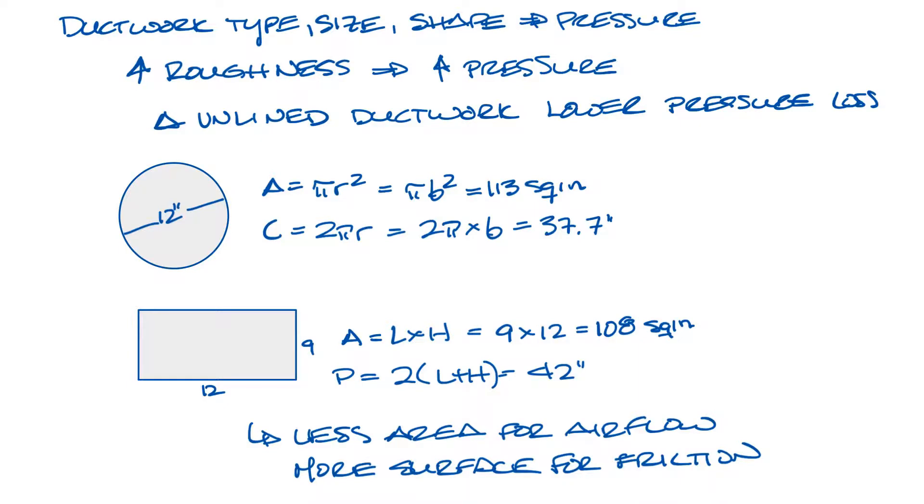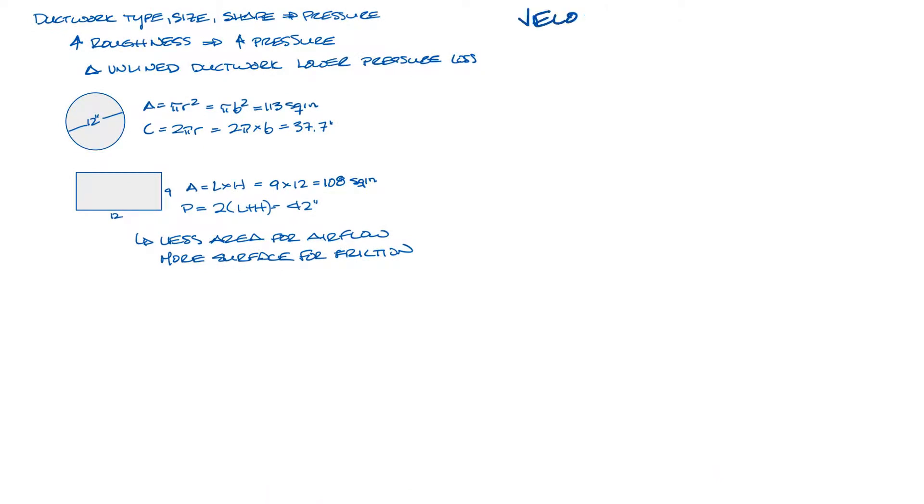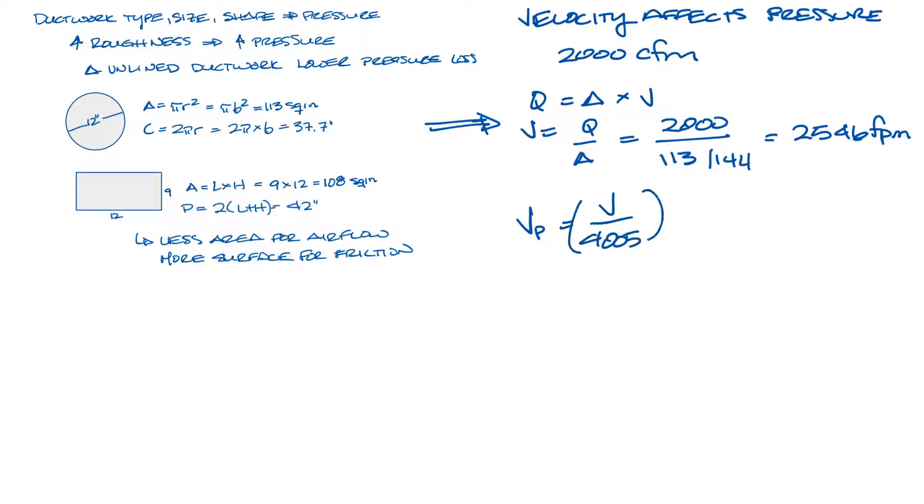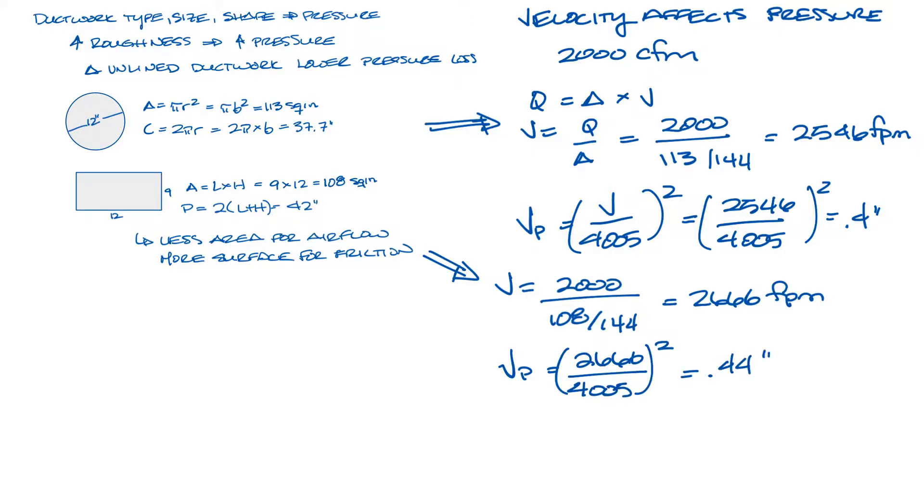The velocity of the air as it passes through the ductwork affects the pressure drop as well. So let's say we have 2,000 CFM. So q equals the area times the velocity, so velocity equals the CFM over the area. So in our circle, we're looking at 2,000 divided by 113 divided by 144 to get it into feet, comes up with 2546 feet per minute. That equates to a velocity pressure, using the velocity pressure equation, of 0.4, which is velocity pressure is the square of velocity divided by 4005, equals 0.4 inches. For the rectangle, the velocity will equal 2,000 divided by 108 divided by 144, which is 2666 feet per minute. And then we can calculate the velocity pressure of that to about 0.44 inches, which is about 10% higher than in the round duct.